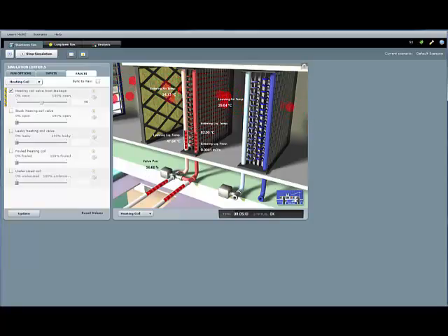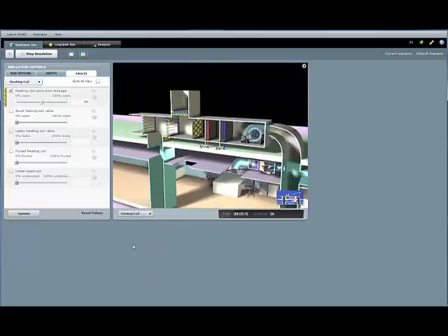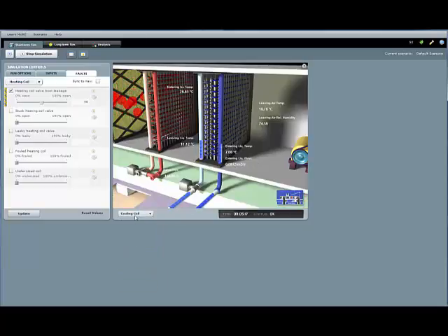And then the cooling coil has to work harder, cooling down from 29 C to 14 or 15 C. So we see we have a system functioning in first heating and then cooling. Now this is an example of a fault that can have disastrous consequences for the efficient operation of the building.